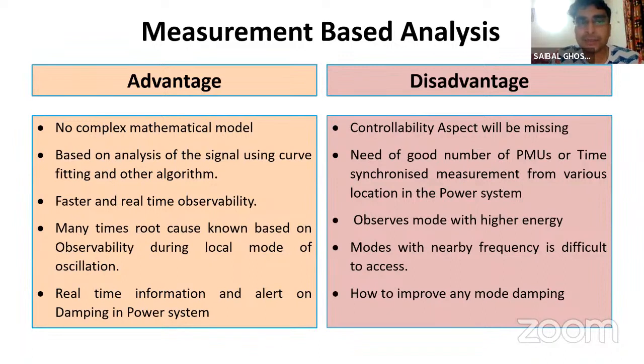Now, as mentioned, if you detect the problem in real time, you don't have any controllability over it beforehand. So only after you notice the oscillation can you take some action. But in model-based analysis, if you see there is some scope for further PSS tuning to damp the oscillation, you can do it before the oscillation even occurs. In measurement-based analysis, once the oscillation has come, only after that can you take some response.